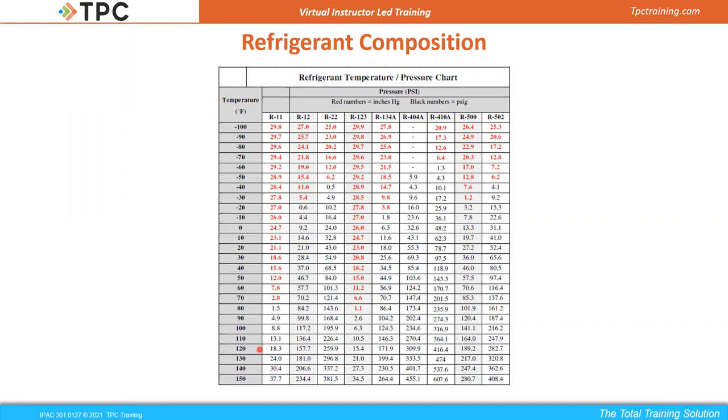Now, of course, that temperature that it's condensing at will be different according to your environment. I just spoke to a guy yesterday that was from Arizona. Temperature there is 105 degrees. So we're going to need a little bit more heat, higher heat content on the outdoor unit. So we're going to be pushing maybe 120, 130 on the outdoor unit. That'll vary according to your environment.